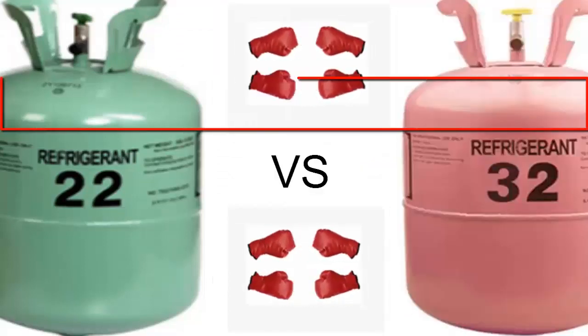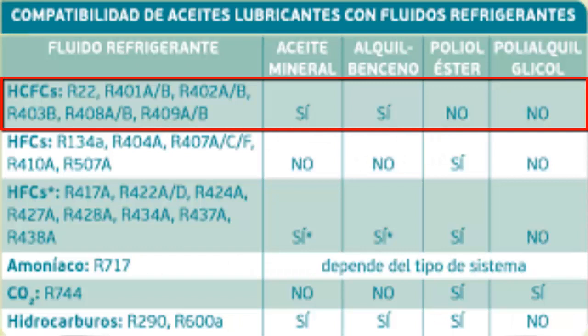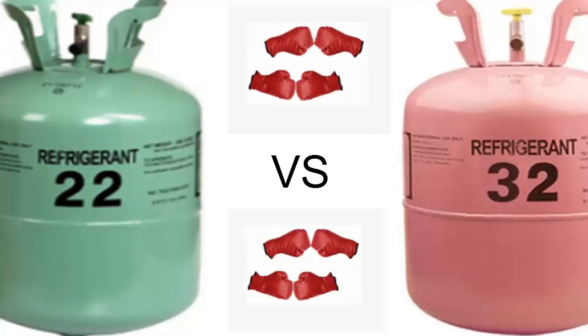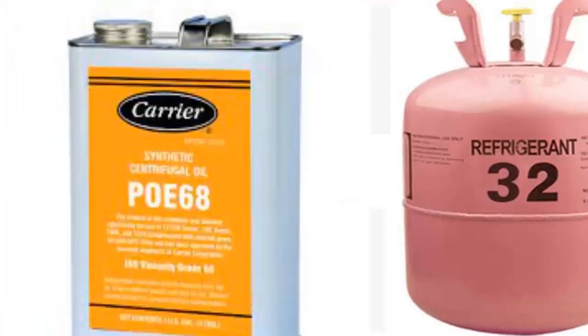Another significant disparity between these two refrigerant agents is their compatibility with different oil variants. R22 is compatible with mineral oil and alkylbenzene, but is not suitable to be combined with POE oil. On the other hand, R32 is congruent and used in conjunction with POE oil.